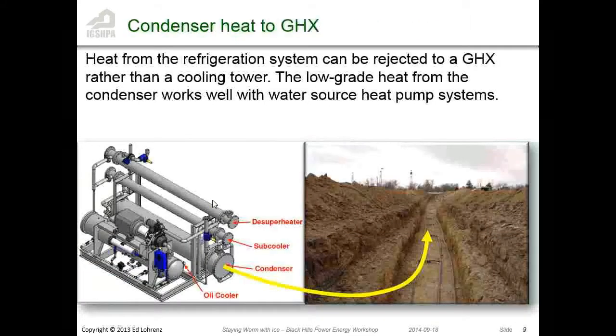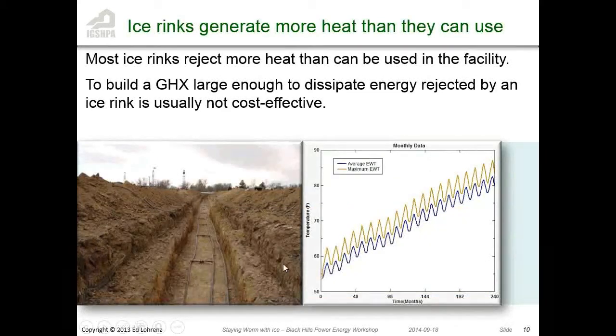You can reject with a conventional chiller. It's not difficult to reject that heat into a ground loop. You can dump that heat into there and then recover it with other heat pumps in other buildings nearby. The problem is, in a lot of places, you've got so much heat that you simply can't use it all. I've seen buildings where you've got 100,000 square feet of building you're heating, and we're still overheating the ground loop. You simply have to get rid of it.